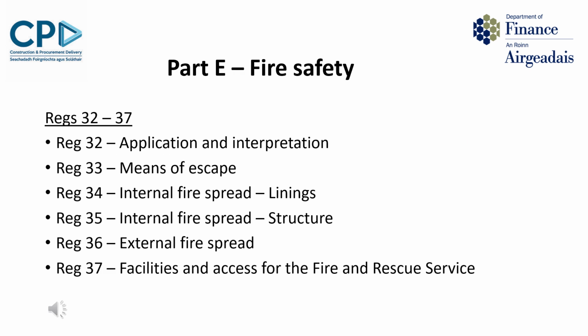Taking Part E first, prior to this amendment, it consisted of 6 regulations numbered 32 to 37. Regulation 32 is the general application and interpretation for the other 5 regulations. So Regulation 33 requires adequate means of escape. Regulation 34 requires adequate resistance to the spread of flame for internal linings. Regulation 35 requires adequate resistance to the spread of fire within the structure of a building. Regulation 36 requires adequate resistance to the spread of fire over external walls and roofs. And Regulation 37 requires reasonable facilities and access to assist the fire and rescue service in ensuring the safety of people in and about a building in the event of a fire.